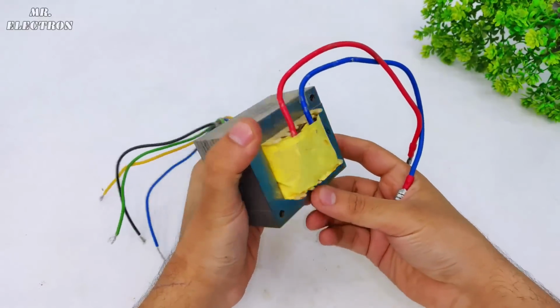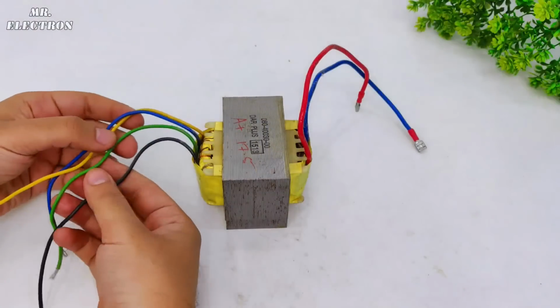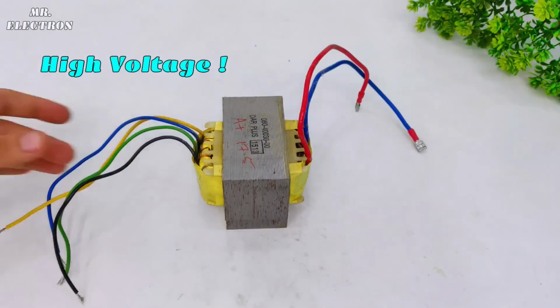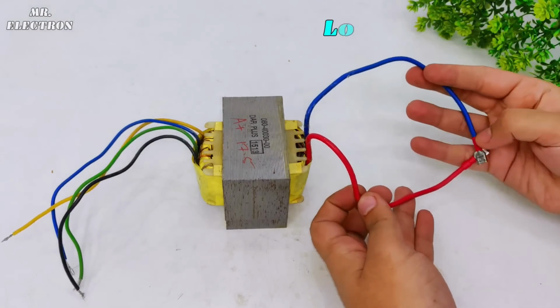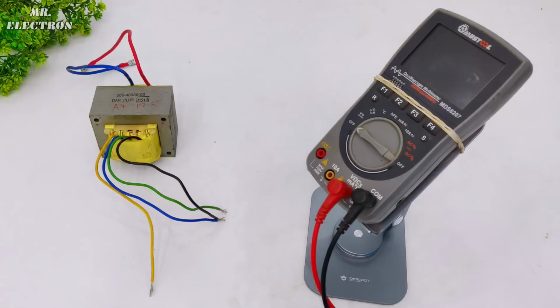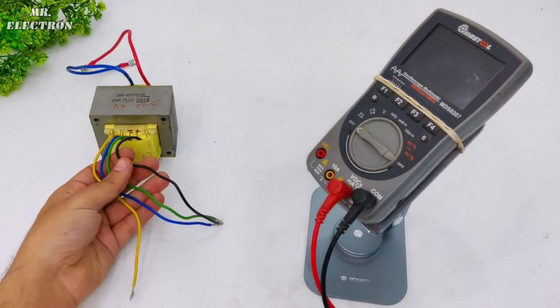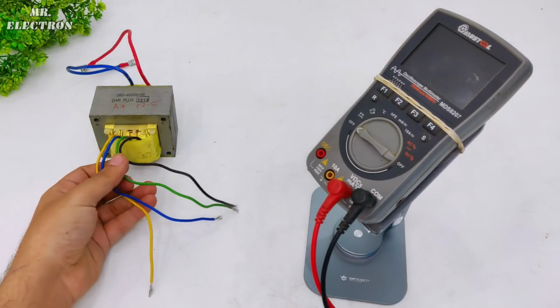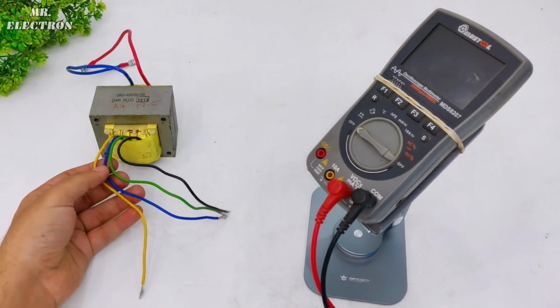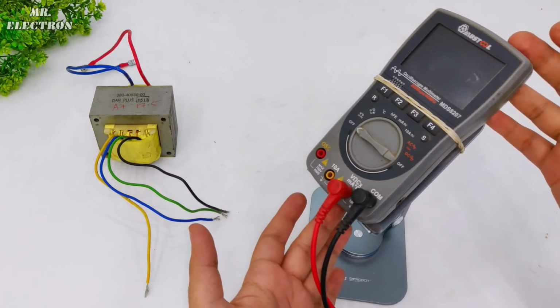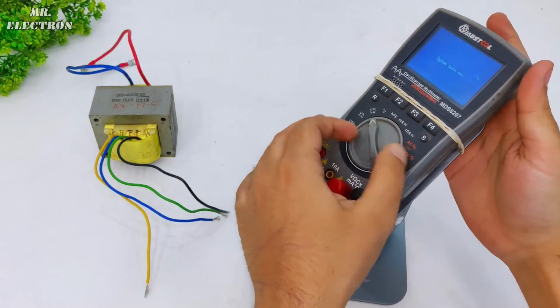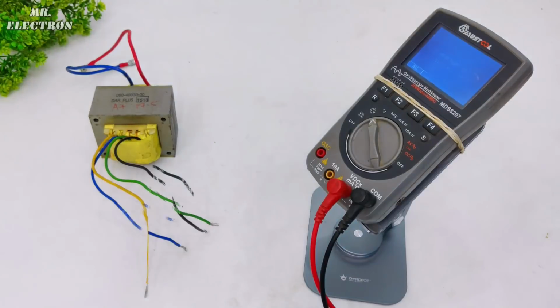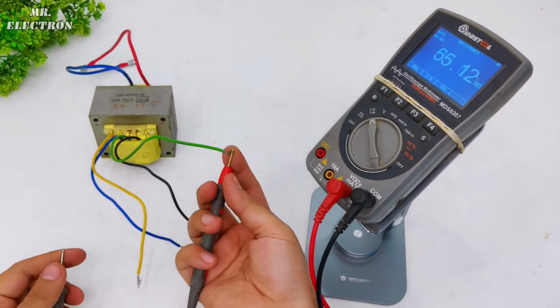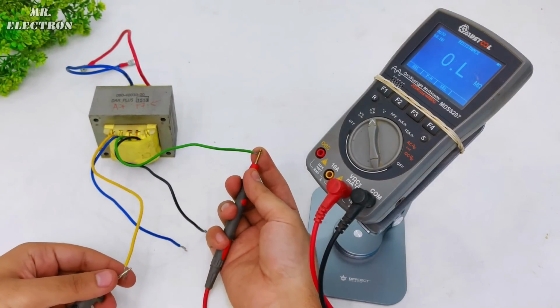This is a computer UPS transformer. These are thin wires for the high voltage and these two thick wires are low voltage. Out of these four, I have to choose only two wires with the help of resistance checking through this multimeter. Let's point it to resistance checking mode.